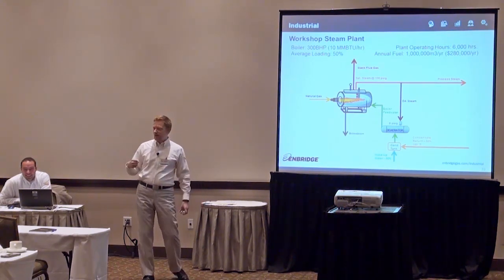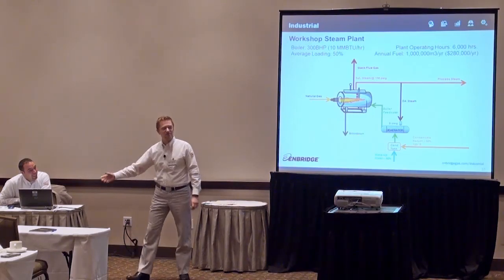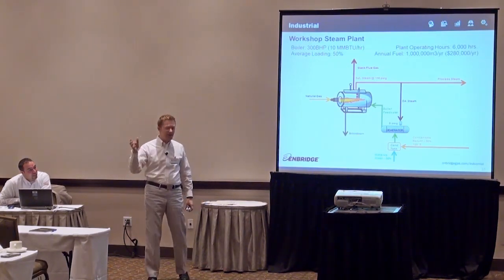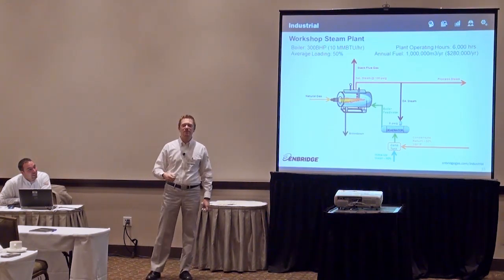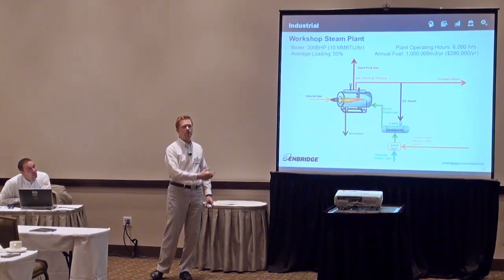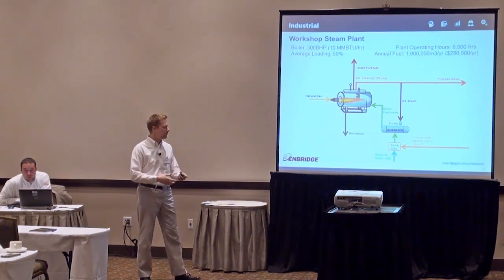And let's say I get sick. I leave that cup, I haven't drunk it yet, I get sick, probably because I took the first sip of that coffee. I go away for a couple of weeks, I come back, I do the same thing, fill it up again. I now have triple concentration coffee. Well, that's functionally what's happening in your boiler. So all those minerals that are coming into the system get concentrated up every time that volume of the boiler is replaced.